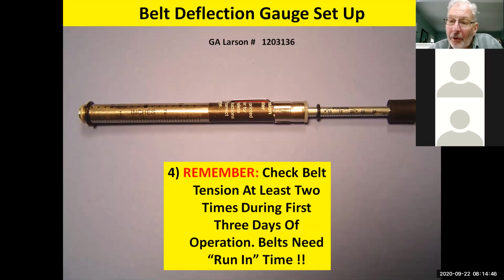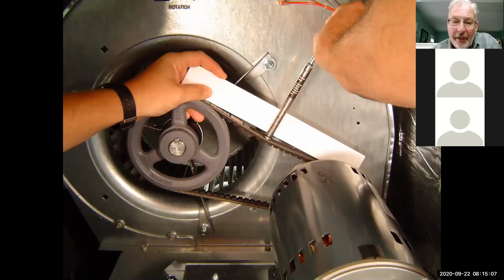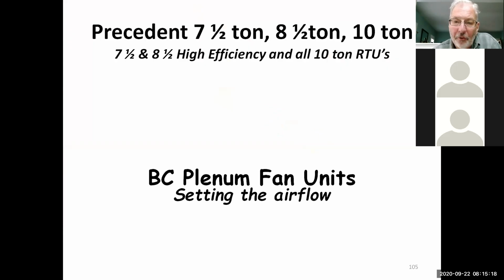Then you and I both know you're not going back on the job 2 days later to go see what the belt's doing. So you give it a little extra tug, pull it tight, and the belt's going to loosen up a little bit over the next couple days anyway. If you're doing belt setup and you're not having issues right now, keep doing what you're doing. This is the factory recommended way of doing it, but I'm not going to change. If the guys got success with it, don't change what you're doing. And that's how you use your belt deflection.